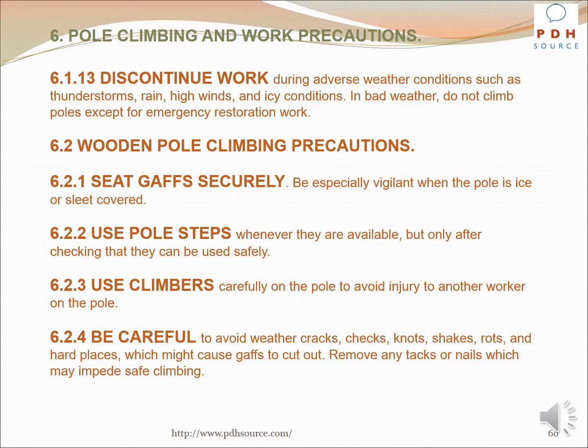Wooden pole climbing precautions include seat gaffs securely. Be especially vigilant when the pole is icy or sleet covered. Use pole steps whenever they are available, but only after checking that they can be used safely. Use climbers carefully on the pole to avoid injury to another worker on the pole. Be careful to avoid weather cracks, checks, knots, shakes, rots, and hard places which might cause gaffs to cut out. Remove any tacks or nails which may impede safety.